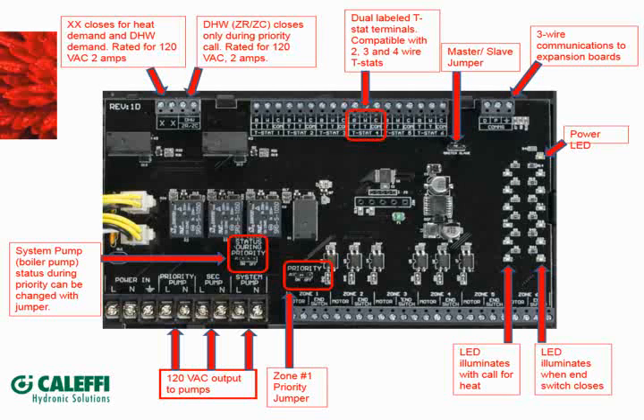Before you leave this one, Mike, a couple questions. Now, it said about the Molex plug on the transformer, so do you really need our transformer to replace it? I mean, yes and no. Ideally, you would get it, but if you notice in this picture, you can see there's a black and white there. A clever person, if you were out on a no-heat call 100 miles from home, and you had another transformer that didn't have a Molex plug, it's pretty obvious that you've got your 120 volt on your black and white and you're switched on that. We'd rather you just use ours so you don't make a mistake there, but yeah. With a voltmeter and a little common sense, you could put any transformer in and just cut that and crimp it in so you had the one with the Molex plug built into it. And then the other question was...